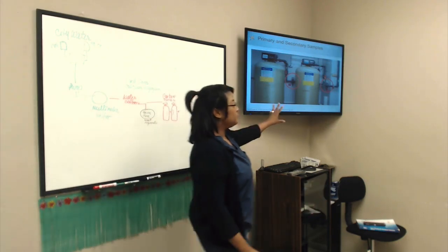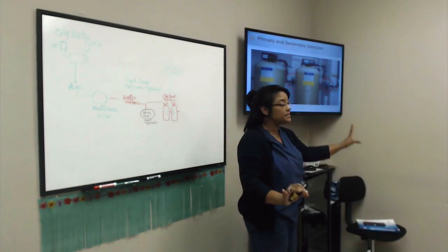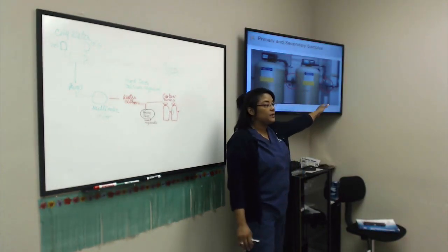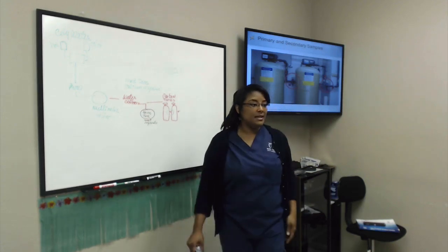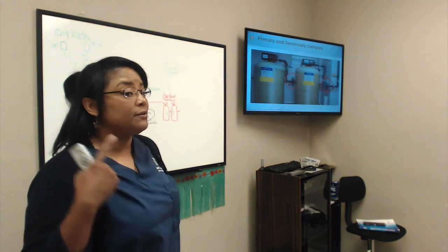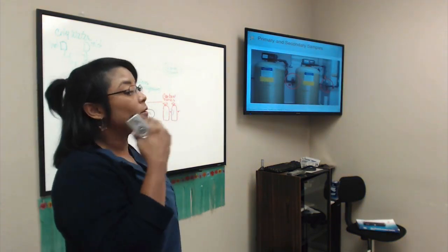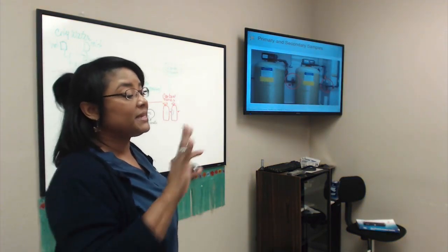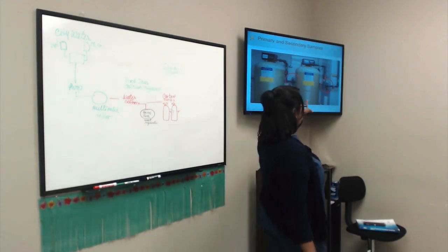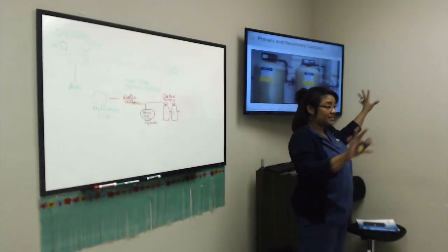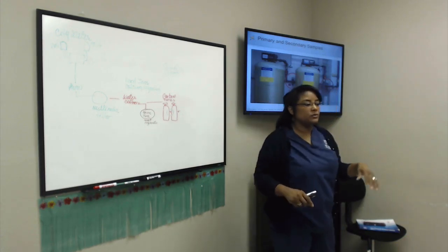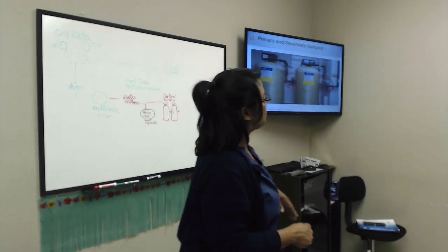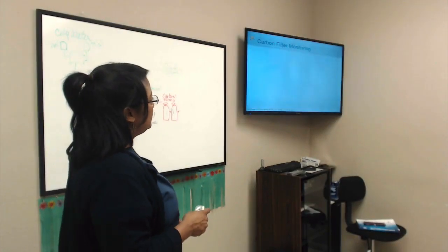The reason for this is, if we're using the second one, this is telling us that we are using just one tank. Does that make sense? We have to try to fix this as soon as possible. That's why we need to report. Because when this one goes out, if it goes out because it got exhausted, we don't have any other tank, so we won't be able to perform dialysis. We will have to stop operations.